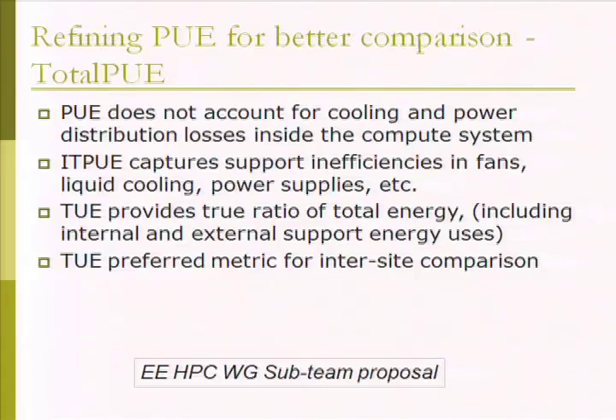The problem with PUE, most apparent in high-performance computing, is that it doesn't account for cooling and power distribution losses inside the compute subsystem. So the EEHPC working group has a proposal. We've written a paper on this, and hopefully we'll present it at Supercomputing, where we want to capture support inefficiencies in the fans, liquid cooling, power supplies, etc., that are oftentimes included in the IT equipment. It'll give a better ratio of total energy, and also make for a better inter-site comparison.